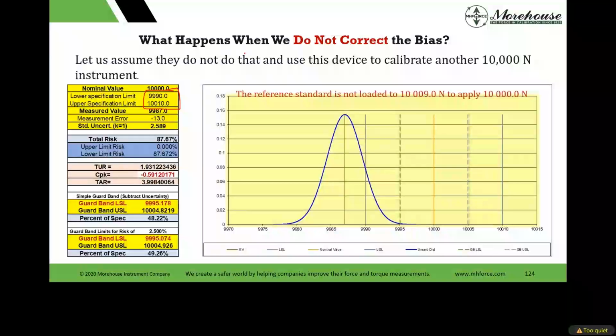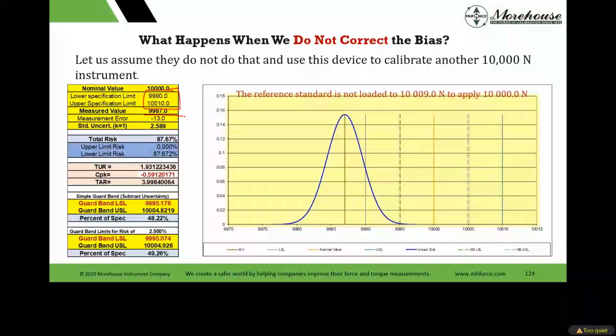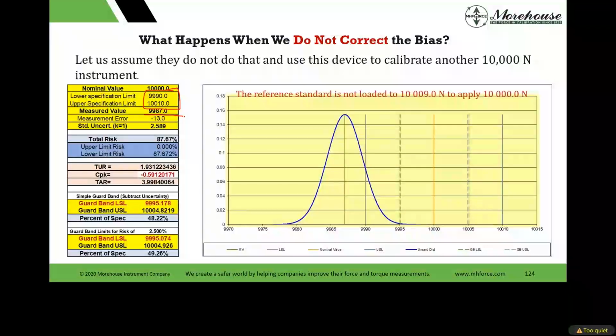And I do not correct. I just program that, and I was off my measured value. I report then to the customer that when I applied 10,000 uncorrected, my measured value was 9987, which is outside of the specification, and then I proceed to adjust the instrument. Now, harder to follow, bit of word salad, which basically means I'm thinking 10,000 is actually 10,000. I programmed these span points. I have the bias. I did not adjust for the bias one bit.